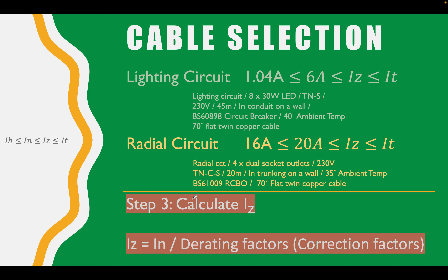We're on to step three, which is calculating our IZ, which is the current carrying capacity of the cable in the installed conditions. We're going to use this formula: the current carrying capacity of the cable, the IZ, is equal to the rating of the protective device, the IN, divided by the derating factors, or correction factors, multiplied together.